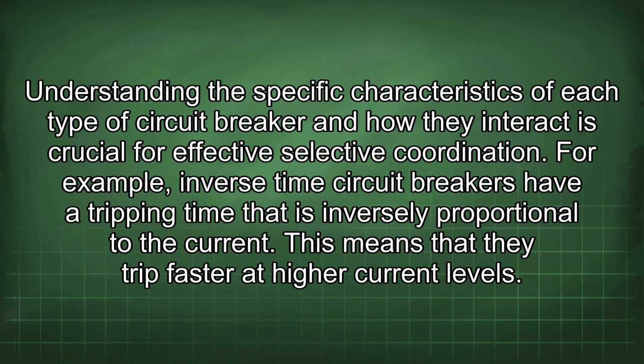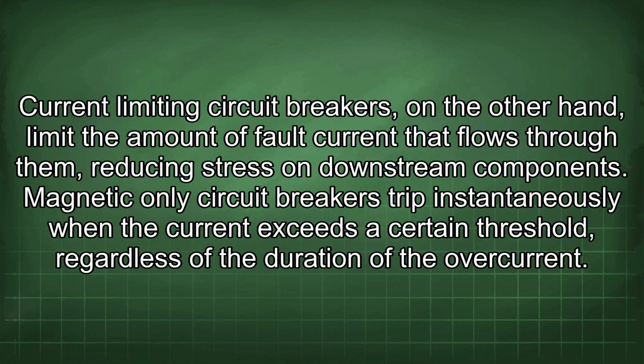Understanding the specific characteristics of each type of circuit breaker and how they interact is crucial for effective selective coordination. For example, inverse time circuit breakers have a tripping time that is inversely proportional to the current. This means that they trip faster at higher current levels. Current limiting circuit breakers, on the other hand, limit the amount of fault current that flows through them, reducing stress on downstream components.